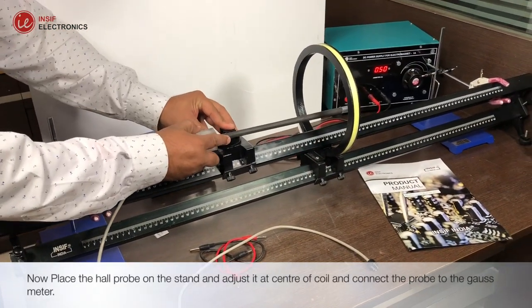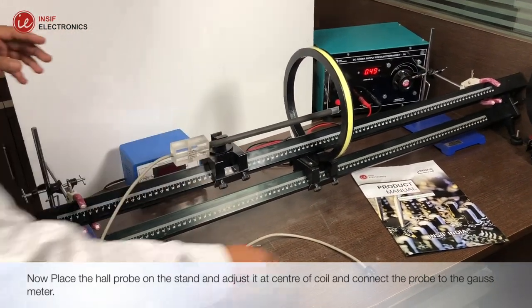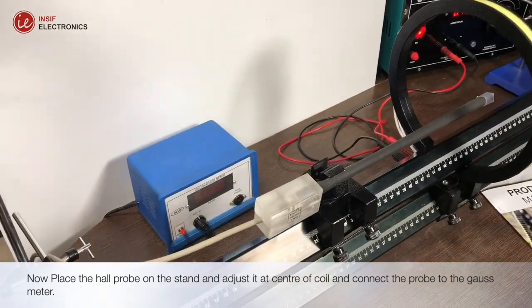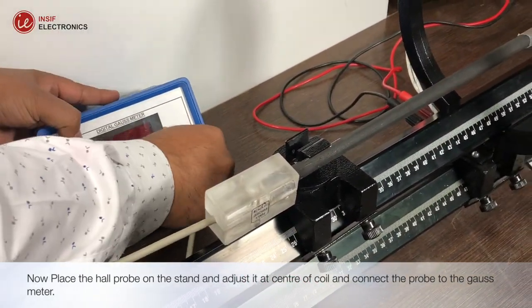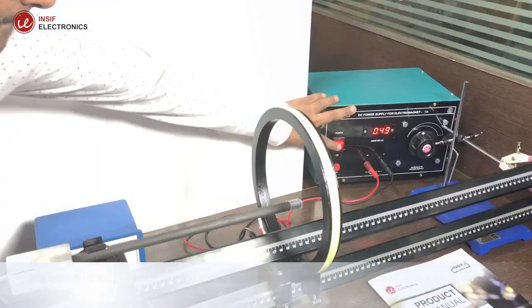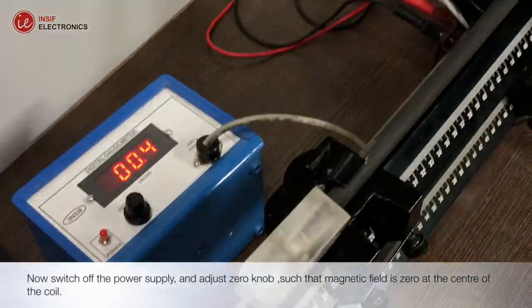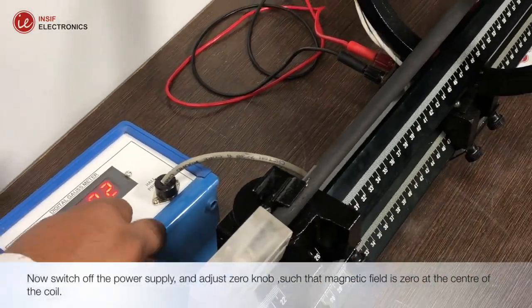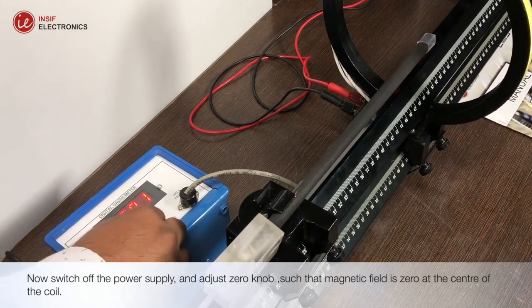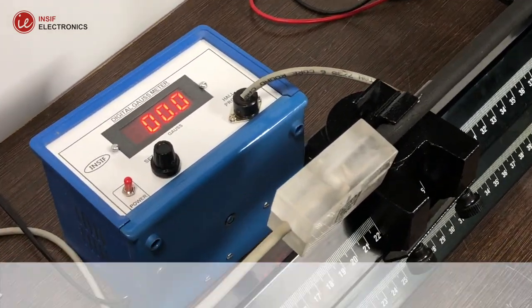Now place the Hall probe on the stand and adjust it at the center of the coil and connect the probe to the Gauss meter. Now switch off the power supply and adjust the zero knob such that the magnetic field is zero at the center of the coil.